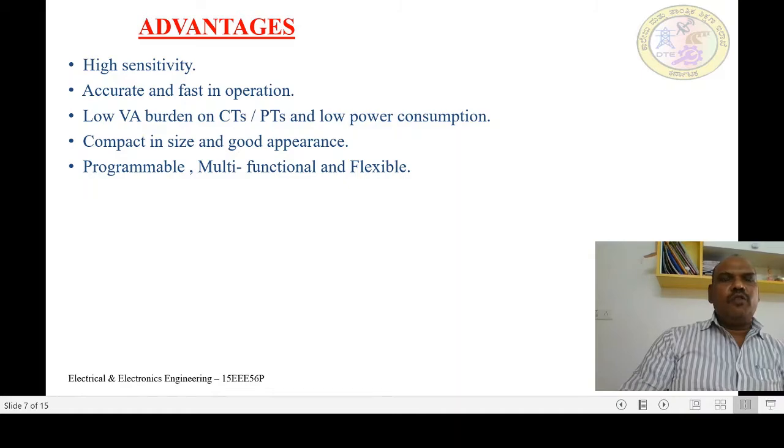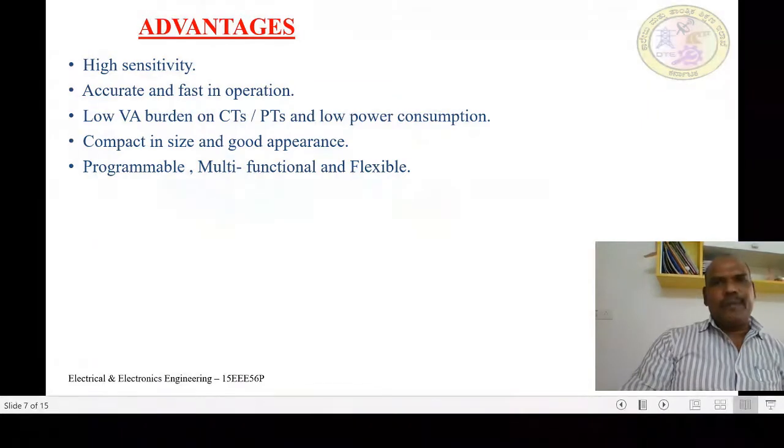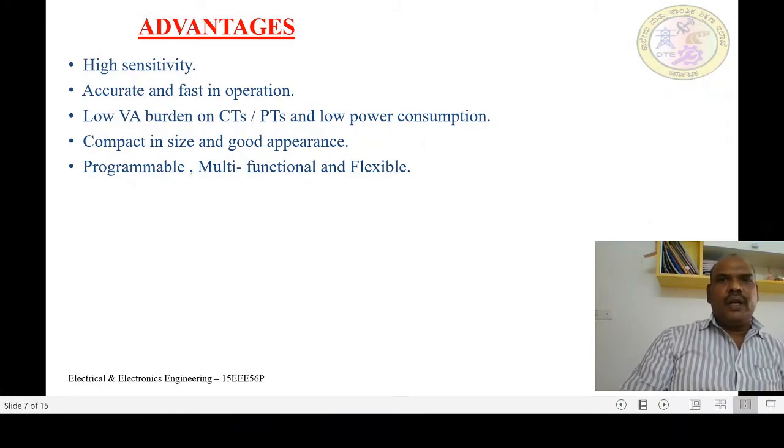See, whenever this multifunctional, as it is mentioned there, where you can use it as a definite time relay, you can use it as a normal inverse relay, and there are many other functions that are available. That is why they are called as multifunction relays. They are flexible because any changes can be easily adapted. It is only a matter of changing the program in the microcontroller for making any changes. So that is why they are flexible. Self-testing. These relays periodically test themselves for its proper operation.